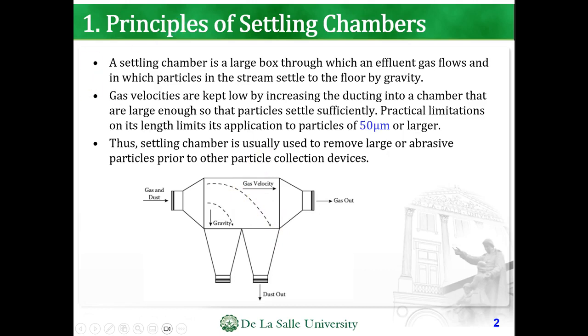Gas velocities are kept low by increasing the ducting into the chamber, large enough so that particles settle sufficiently. Practical limitations on its length limit its applications to particles of 50 microns or larger. Settling chambers are usually used to remove large or abrasive particles prior to the particle collection devices.